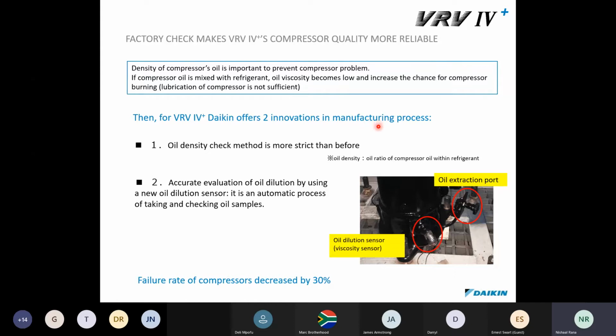So what do you need to do? You need to have oil density checks. Methods must be more strict. You probably do it, call me a liar, but maybe every 6 months or every year, or at a major service. So it's also accurate evaluation of the oil dilution by means of a new oil dilution sensor, right? These are the kind of things that need to be done, and we've got these oil viscosity sensors now that are also put into our new VRV IV+. So what does that mean? By changing oil, by doing preventative maintenance, you can reduce the failure rate of compressors by 30%.